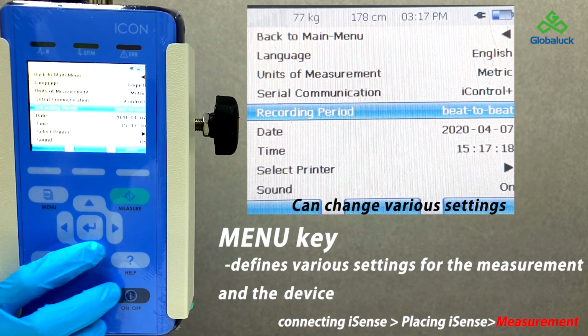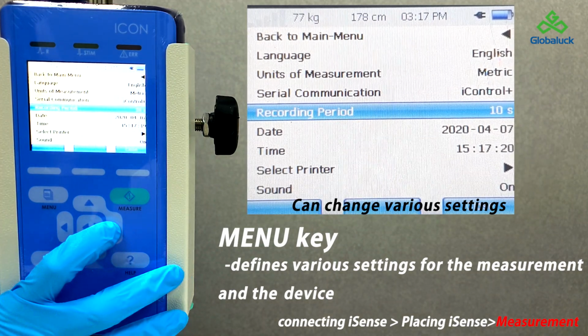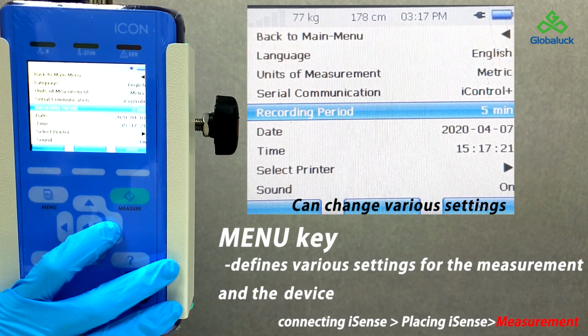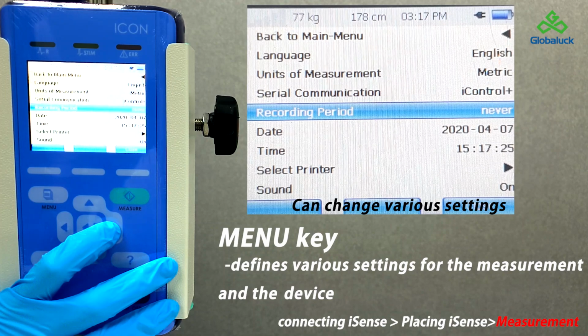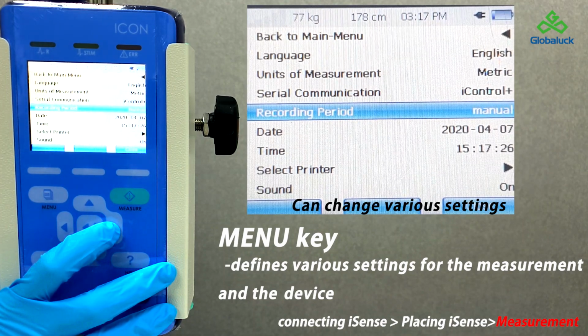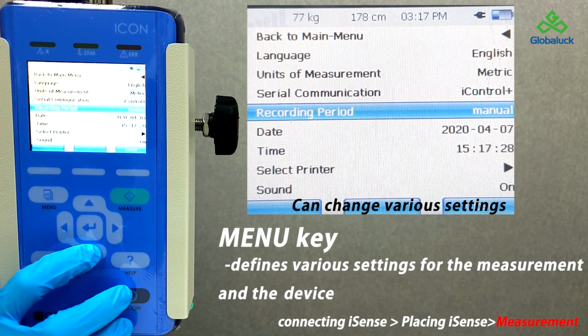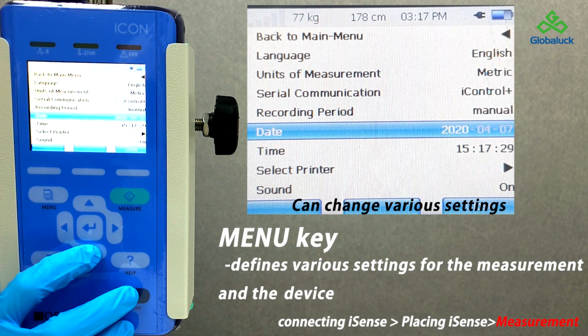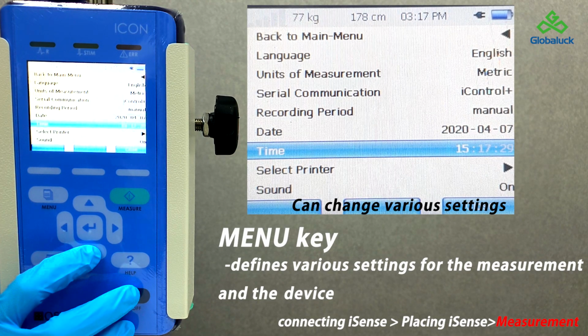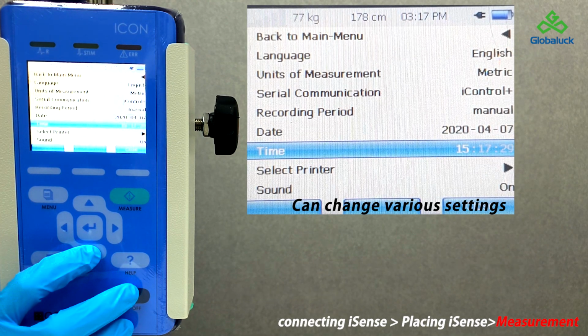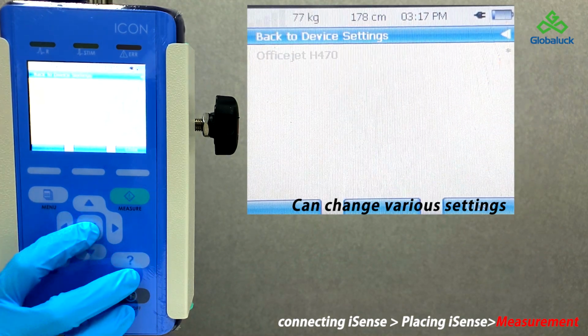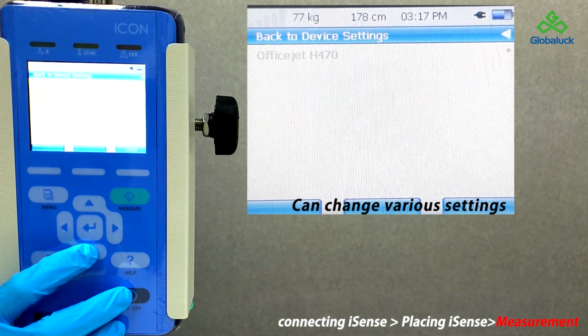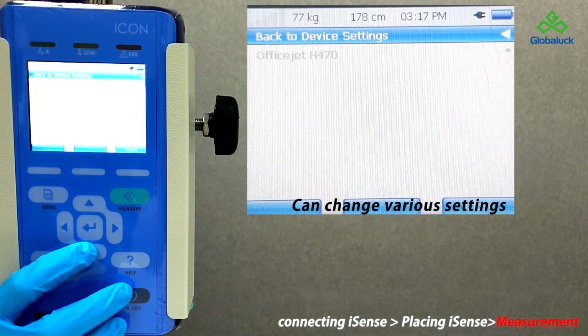Recording period selects the interval, from beat to beat to 1 hour, at which numeric hemodynamic parameters will be saved on the icon internal memory. Data saved on this memory may optionally be exported to a PC. Date and time allows the setting and adjustment of current date and time. The icon will be reset to its factory defaults if the battery is dead, so you should set the date and time again. Select Printer searches and selects a printer for use in the Print Report function. The printer must be Bluetooth compatible.